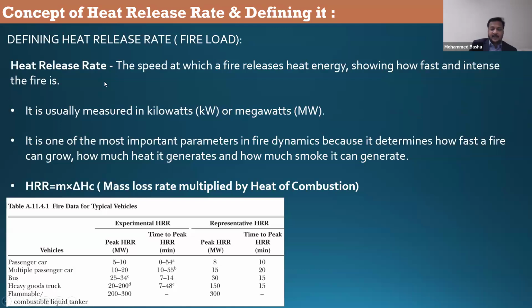So I have explained to you what is heat release rate, which is the speed at which a fire releases energy. You can see some data which is taken from NFPA 502. This is for tunnel fires. You can see passenger car fire, peak HRR, time to peak, representative HRR. You can see 8 megawatt or 5 megawatt, buses 25 megawatt, heavy goods trucks 200 megawatts, flammable combustible liquid tankers 300 megawatts. So this is the type. So if you are designing for car parks, we have the ready data, right? Car parks or bus park, everything we have.